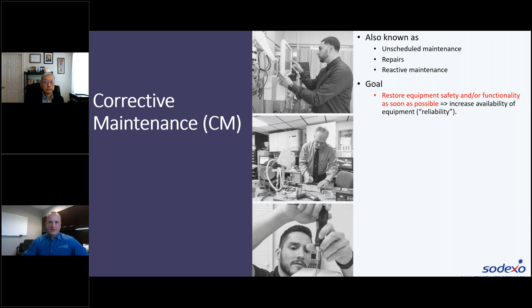Corrective maintenance, also known as unscheduled, corrective, repair, reactive. Our goal here is to restore the equipment to its operating conditions as intended by the OEM for safety and functionality. Again, what are we looking at here? Reducing downtime, detecting failure causes to prevent other actions, detecting failures in progress, and hidden failures. So after we do a repair, we want to make sure that we do a safety and performance evaluation of every device.